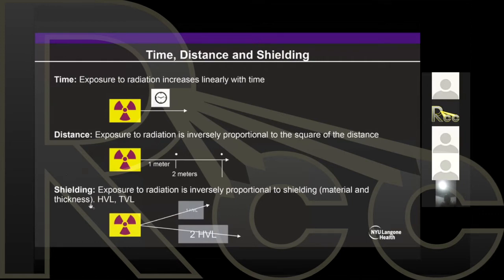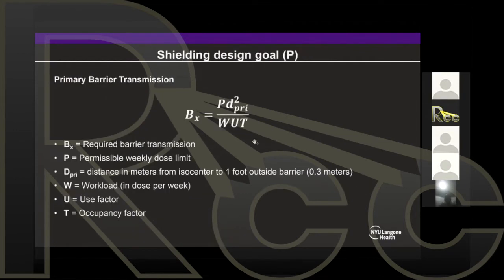And we normally will talk about half value layers, tenth value layers. So you can see here, if you are behind this barrier or behind this barrier at the same distance, you will be exposed to half of the radiation. So I mentioned earlier the shielding design goal, right? I just wanted to show you where this comes from, what the formula is, for instance, for the primary barrier transmission, because it's important to know, even if we're not going to do shielding calculations directly, which factors are involved in case you need to look back and see why a measurement might not be as good as you thought.